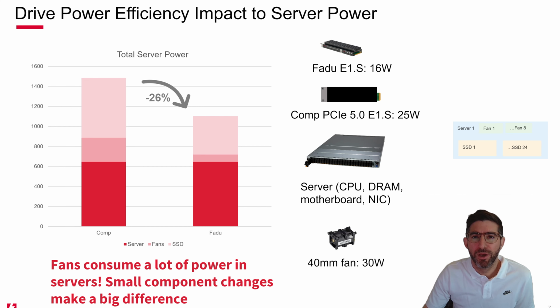Now, why do they do this? With an E1.S, you can basically cool the drive. The 15 millimeter and 25 millimeter have nice heat sinks on there, and you can run the fans at a much lower speed. And the drive temperatures can operate pretty high, up towards whatever the limit of the operating temperature range is, because NAND actually likes to be hot. It's actually the controller that you're really worried about as far as controlling operating temps. And most of the temperatures on the drive are mandated basically by a technician being able to hot plug the drive. It's literally case temperature, so that somebody doesn't burn their hand.